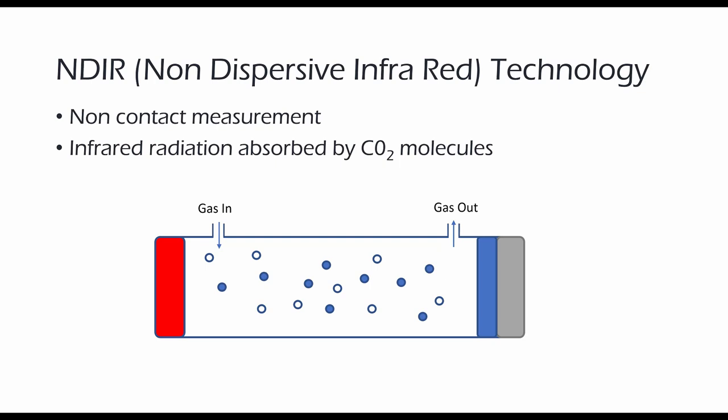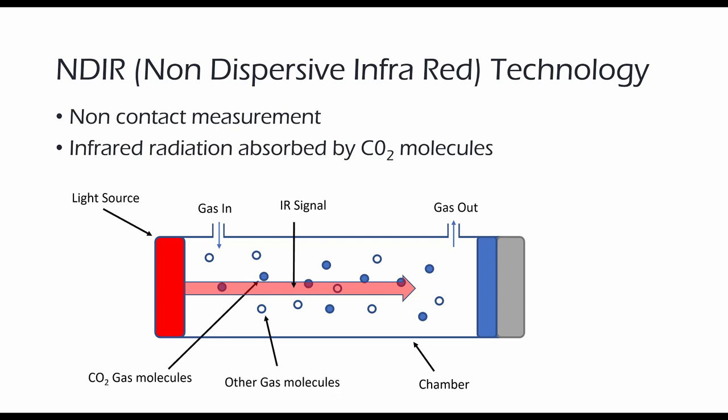This works on the principle where infrared radiation is absorbed by CO2 molecules. So an infrared light, which is a source signal, passes through a chamber that consists of the gas. In this case we're trying to detect CO2. And at the receiving end is a detector with an optical filter in front of it, which is selected to take in the wavelengths associated with the CO2.